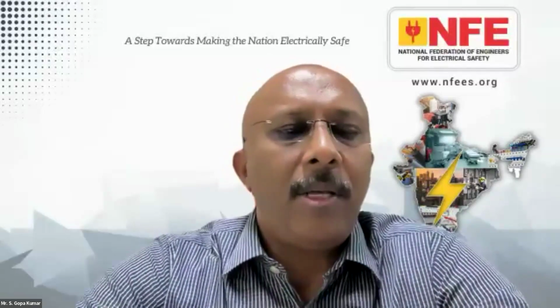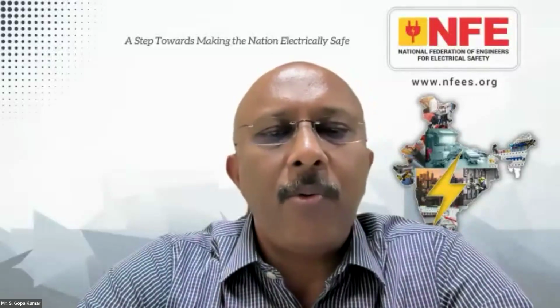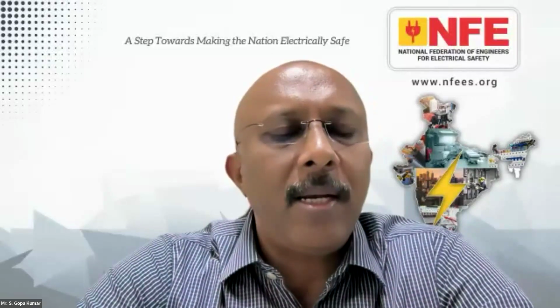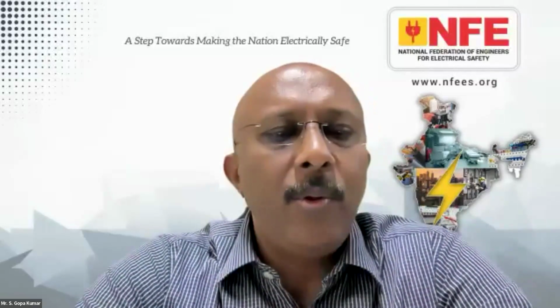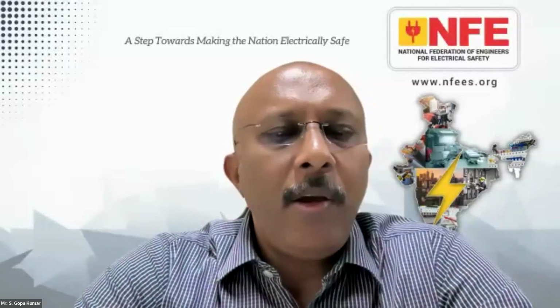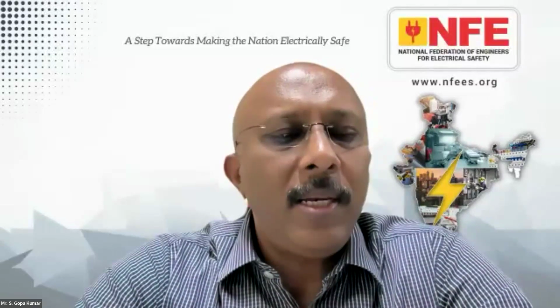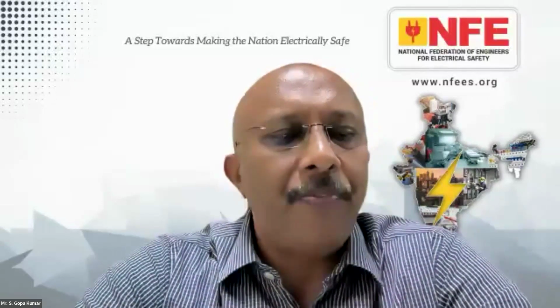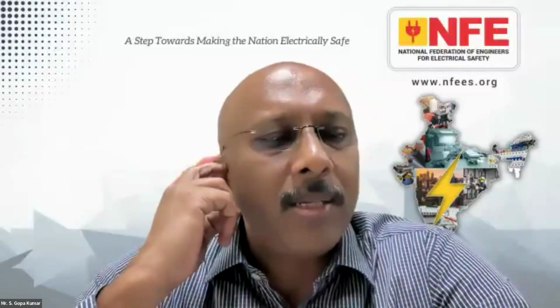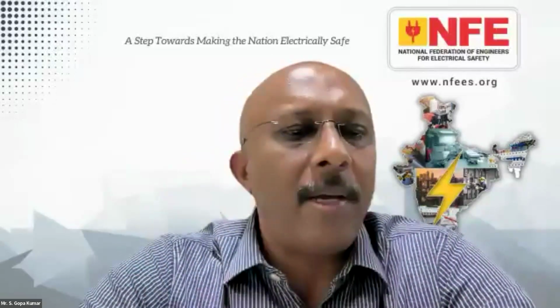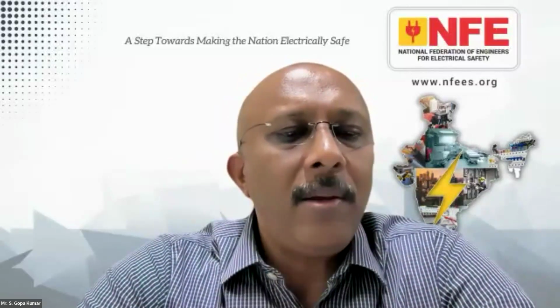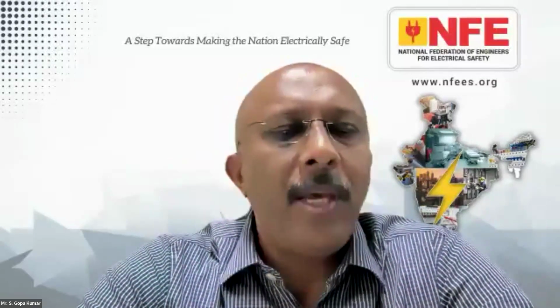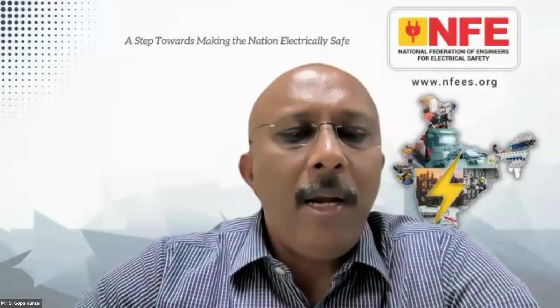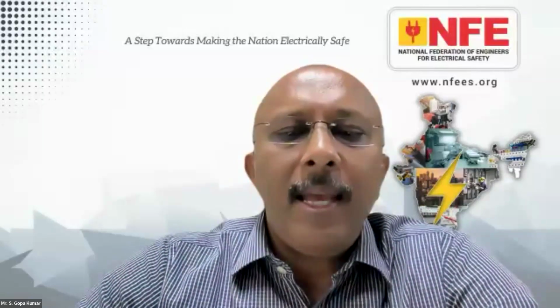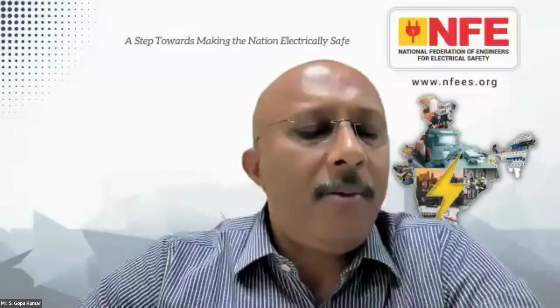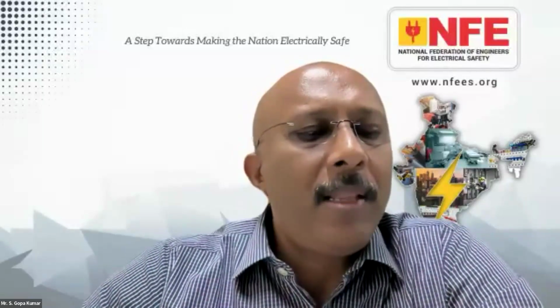So these sizings are already there in the standard. If you are going for a TNS system, this earth conductor must be connected to the neutral of the transformer. Now, if you have your own transformer and your own DG set, you must follow a TNS or TNCS system. But basically, both are the same. In TNS, there is a metallic fault return path. Now, when an enormous amount of fault current flows, there can be potential buildup in the conductor, and we have to handle that by way of equipotential bonding within the building.